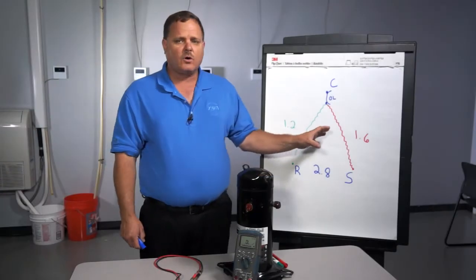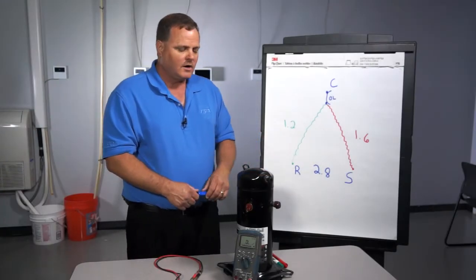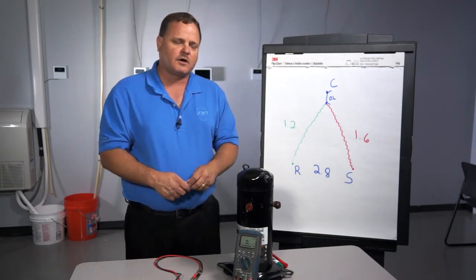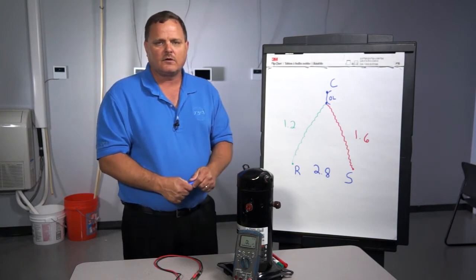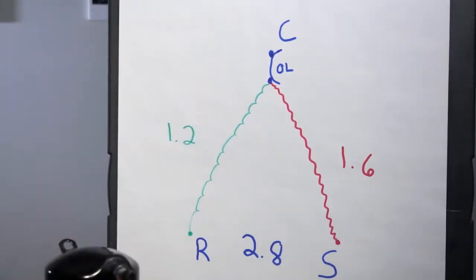These are the actual ohm values of this compressor. The ohm values are fine, the compressor is good. But I want to talk about ohming out a compressor when you have a short or ground and how the readings should play out.